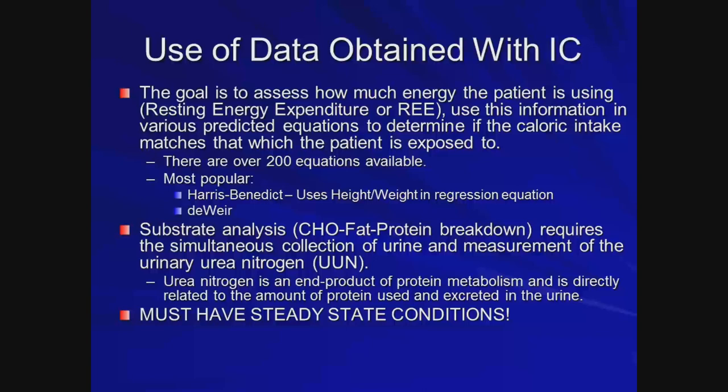The key requirement is a steady-state condition. You hook the patient up to the indirect calorimeter, dim the lights, and measure them at rest — don't disturb them. It takes about 20 to 30 minutes to get a stable reading, and from that point you can derive your values.